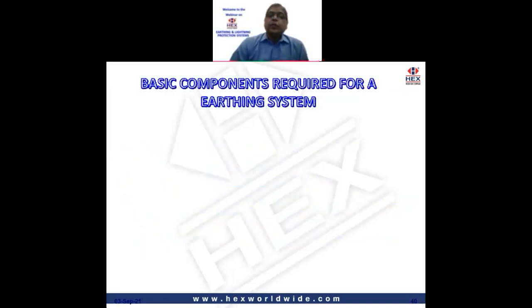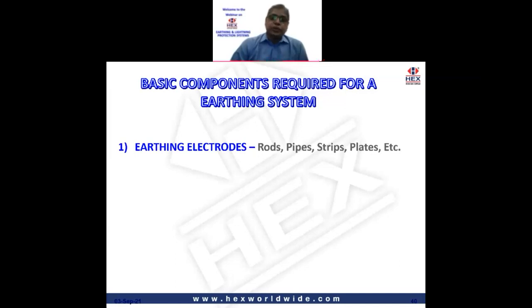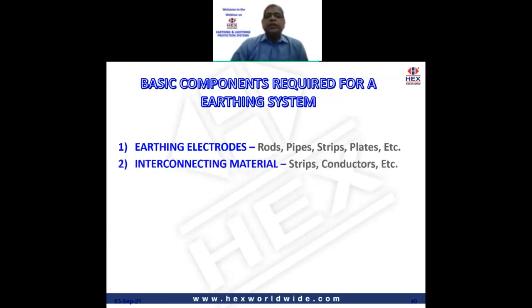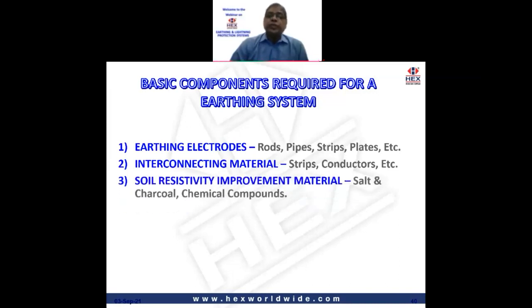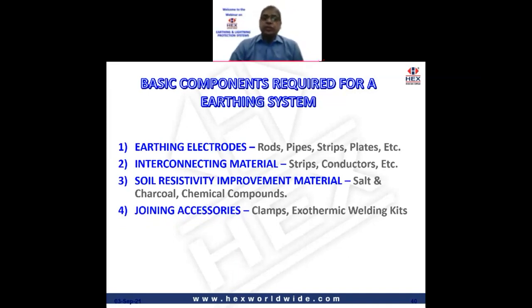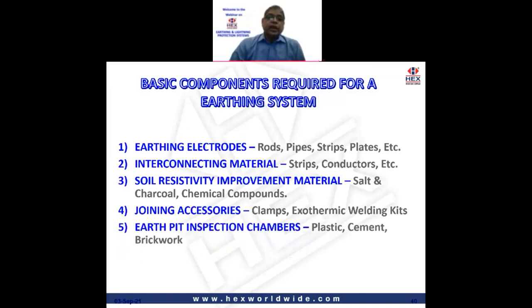What are the basic components required for an earthing system? You must be knowing this also. Earthing electrodes, which can be either rods, pipes, strips or plates. Then we have the interconnecting material, which are the strips and conductors. Soil resistivity improvement material, where many of you are still using salt and charcoal, and then chemical compounds. Joining accessories, which can be clamps or exothermic welding kits. And earth pit inspection chambers, which can be plastic or cement ready to be used, or maybe the brickwork is done on site.